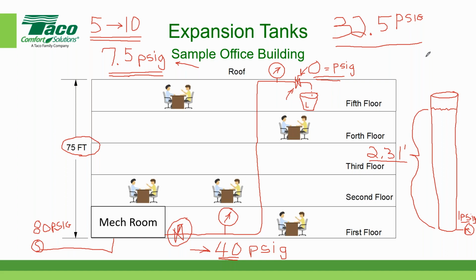Well, it's the pressure at the top of the building. It has nothing to do with the furthest point. It's simply the pressure at the top of the building. We're not circulating any water yet, so we're not trying to get water to the end. This water is not moving. All I did was set the pressure from the bottom of the building. In a minute, I'm going to show you what happens when we start moving.